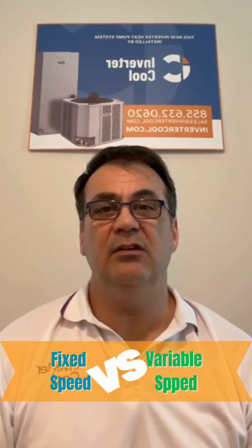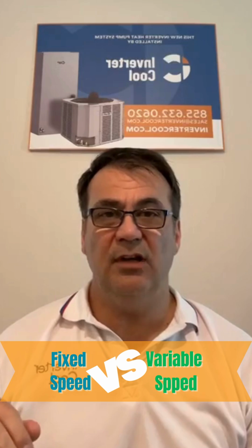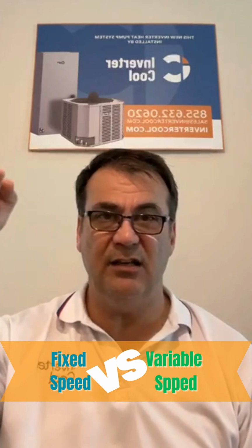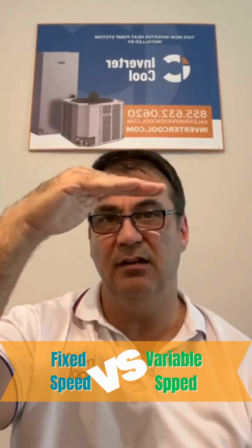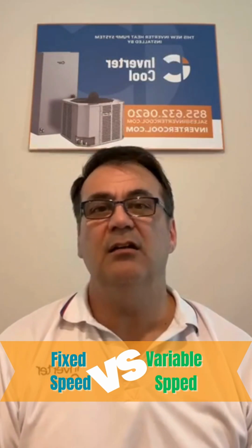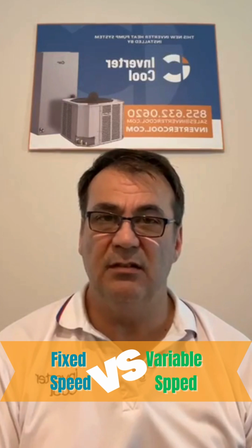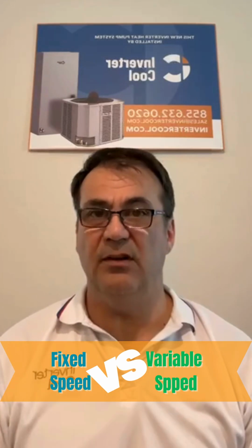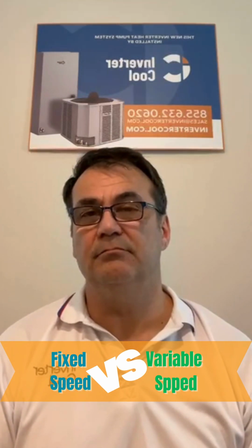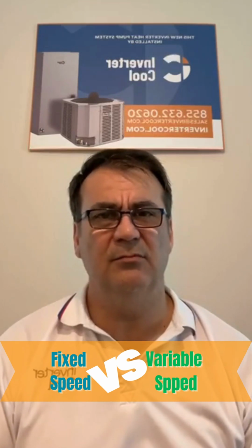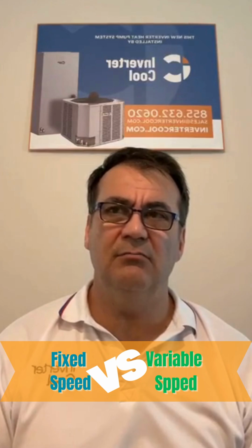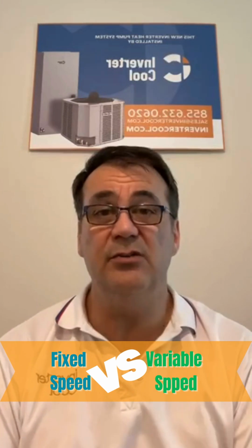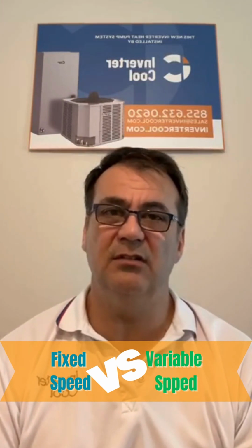And then we run it through a rectifier that will help smooth off the valleys so that eventually you end up with a straight line of pure DC voltage. That voltage is pulsed to the compressor in different frequencies so that it can run at different frequencies, saving you money. So anyway, that's a technical breakdown of how they work. But all in all, you're not going to save as much money with a fixed speed or a 2-speed compressor as you will with an inverter.